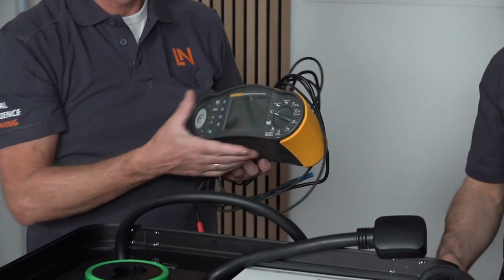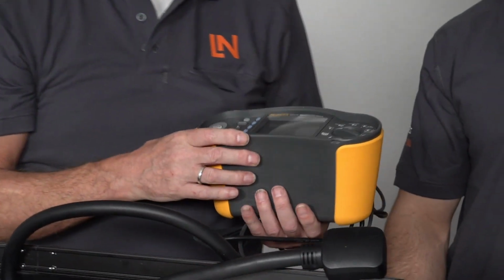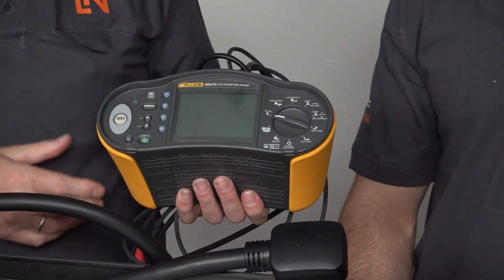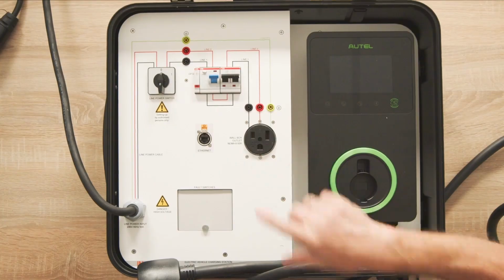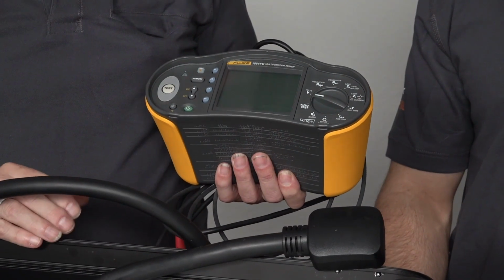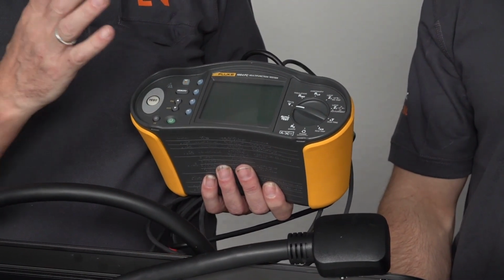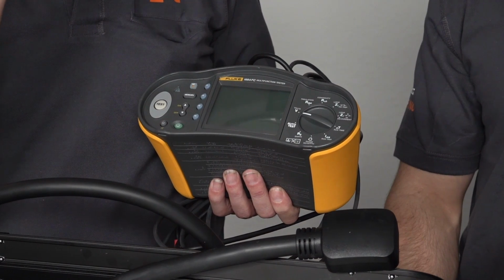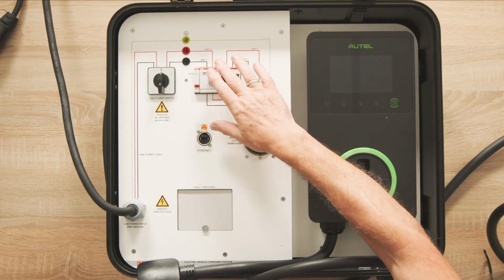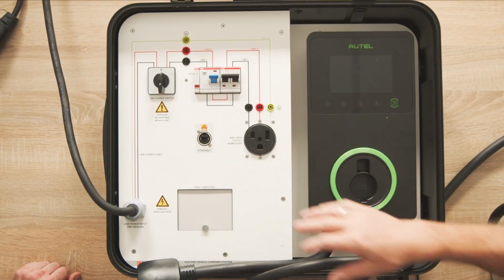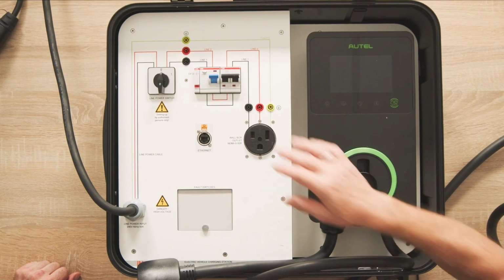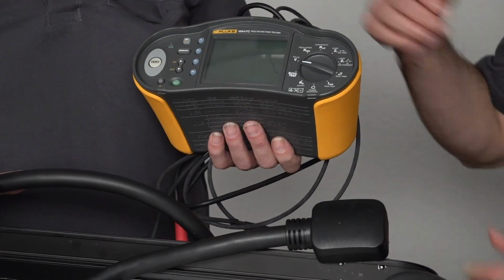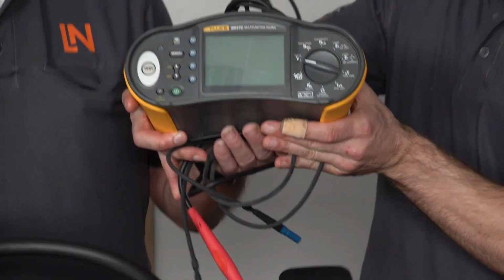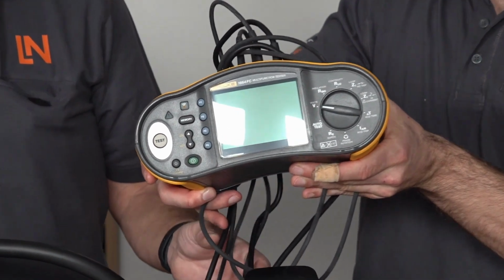We'll keep it succinct on camera. In this case, for instance, a test device is used for testing the entire installation system. That means here the protective conductor test is carried out, here the insulation resistance measurement is carried out, etc. That is, the RCD test, the triggering of the overcurrent protection or residual current protection devices, for example, is being checked. As long as the installation is fine, everything is wonderful.